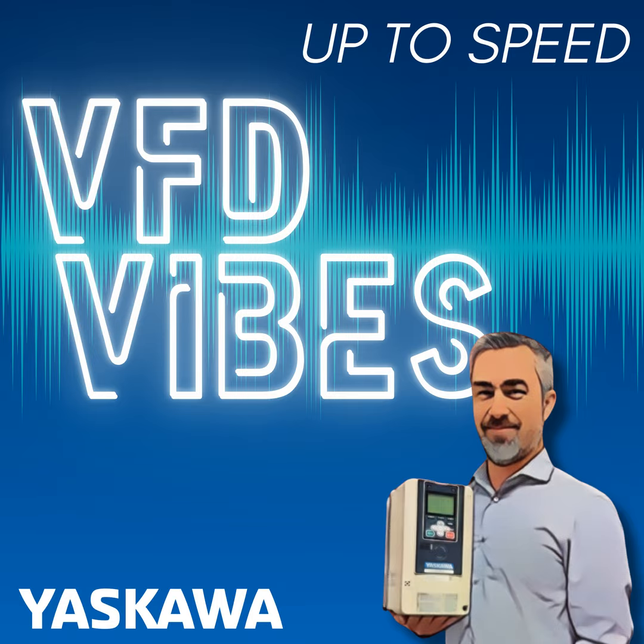Yeah, so some of the safety functionality of the drive gets automatically set with an auto tune. And when you say parameter E2-01, one of the cool things with Yaskawa drives is that parameter is the same no matter which drive family or which drive you're using. So you can commit that to memory right now and you'll never have to learn it again. Good point. Yeah, that goes back to E7, Z1000, and now HV600 and all the other drives on the industrial side as well.